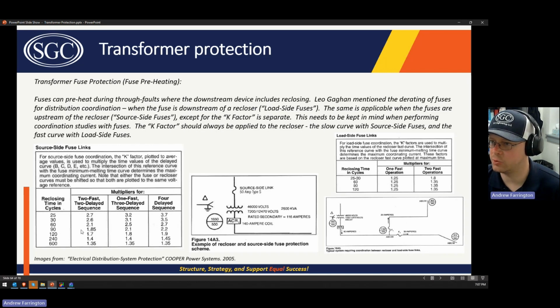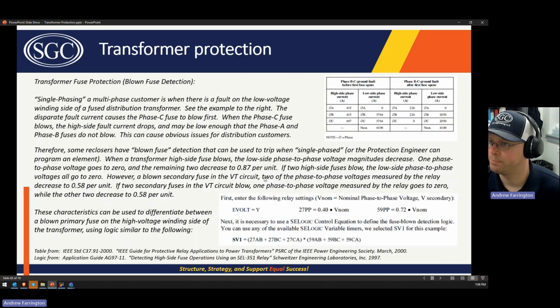What we tend to use more often in power transformer applications is a fused transformer with a low side recloser. If the recloser has, say, a reclosing time of 2 seconds, and maybe you have 2 fast, 2 delayed shots, you would need to apply a 1.7 K factor to the recloser's slow curve, for example. So depending on what you've got for an application, you need to read through this slide, and that'll help you apply the K factor for your coordination study.